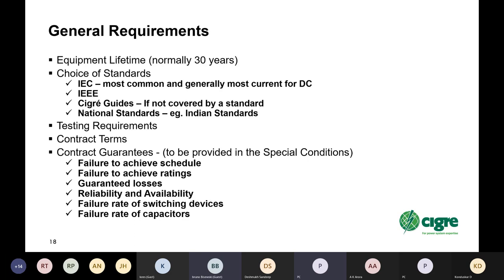You should then decide what are the testing requirements for the equipment. Some owners don't require any new type tests. Others like to have type tests and witness type tests and routine tests. That's something that's more or less an owner preference. We always recommend to use type testing, or to have a certain amount of type testing for quality control.